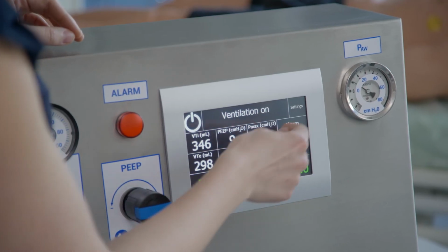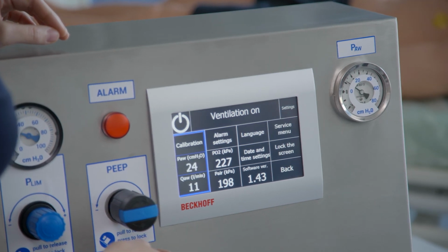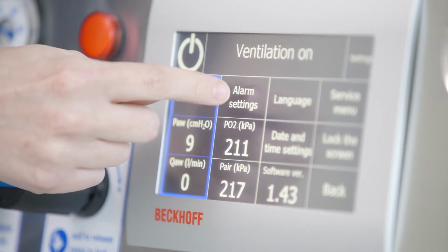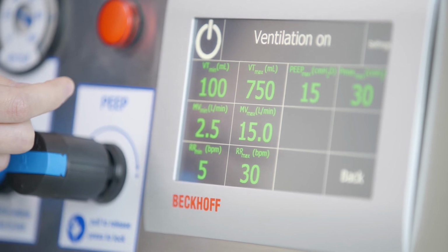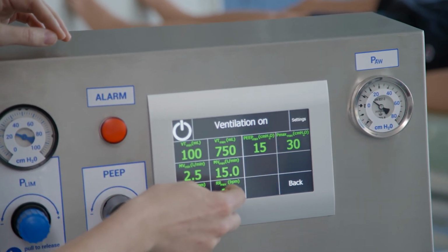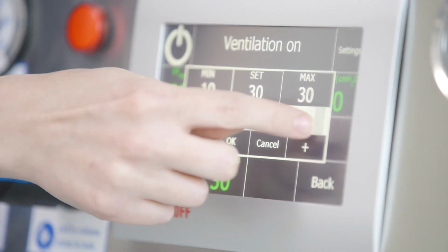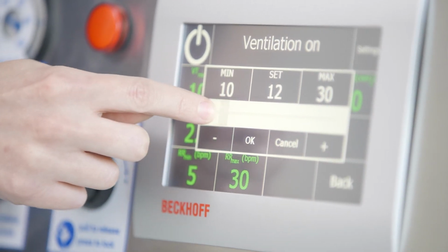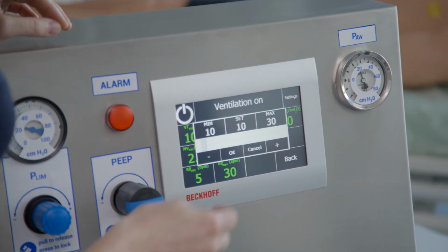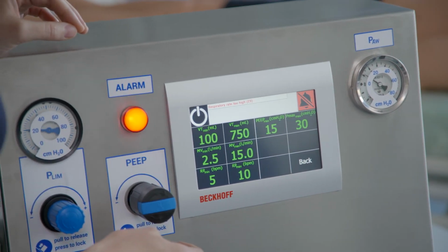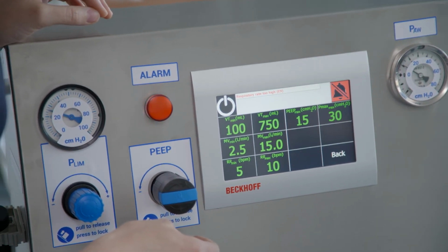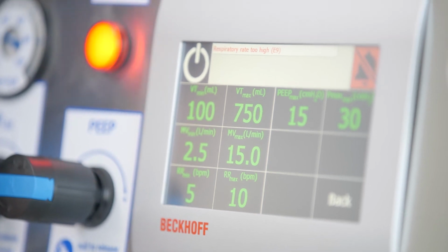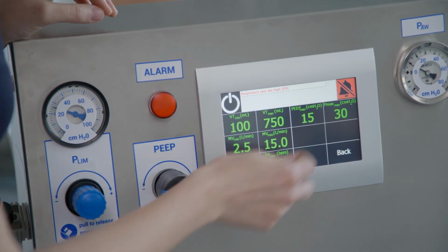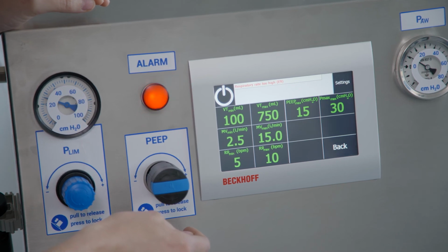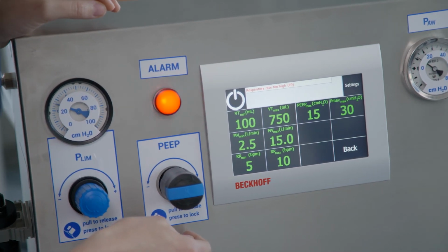For each patient, we should adjust the alarm limits. The alarms are set in the menu Settings and Alarm Settings. There you can see the limits set by the manufacturer. The alarm limits are adjusted in the same way as ventilation parameters. When the alarm limit is exceeded, the sound and visual signal is activated and the alarm text is displayed on the screen. We can mute the sound alarm for 120 seconds using the red bell.